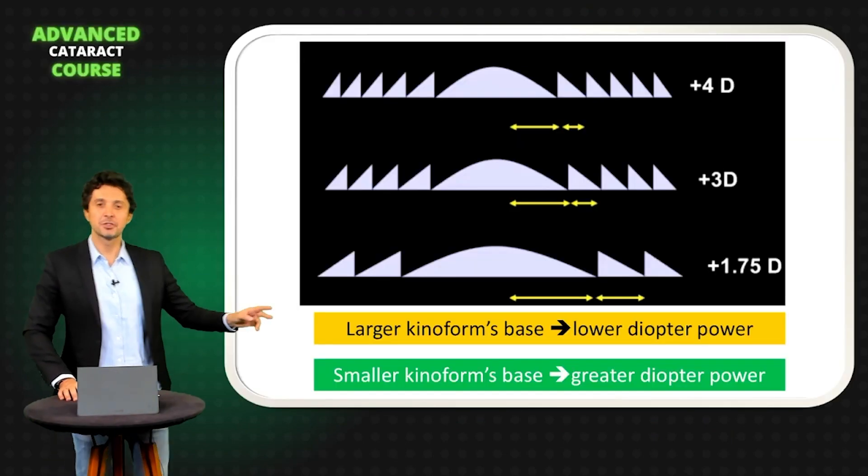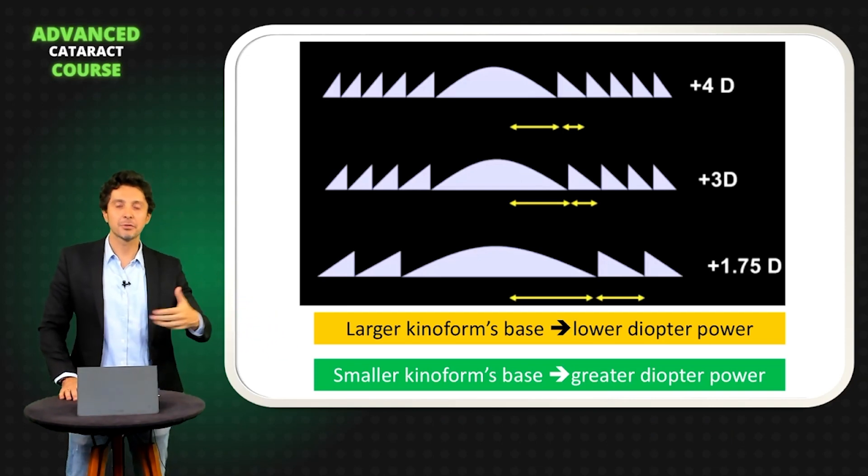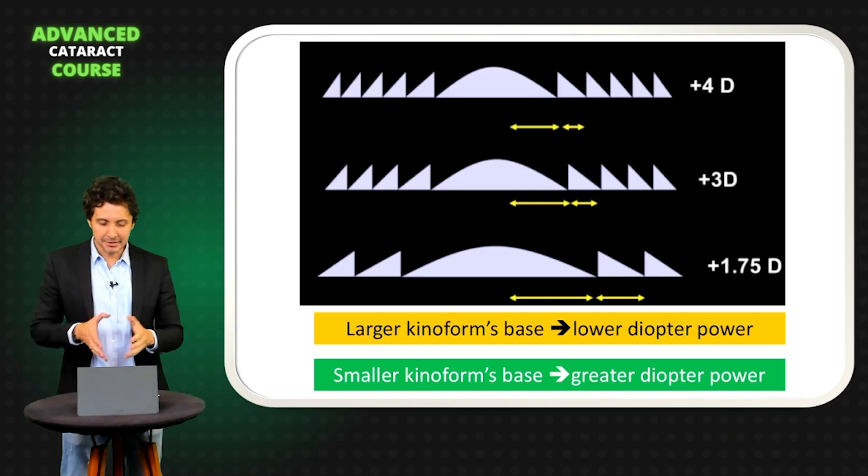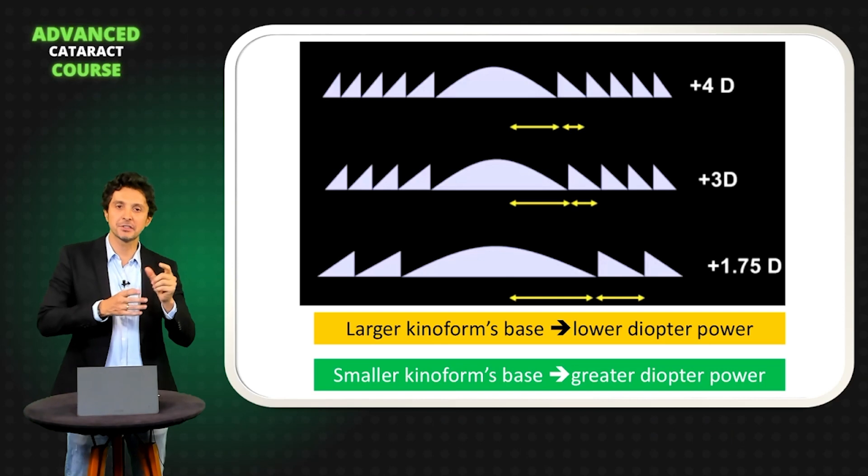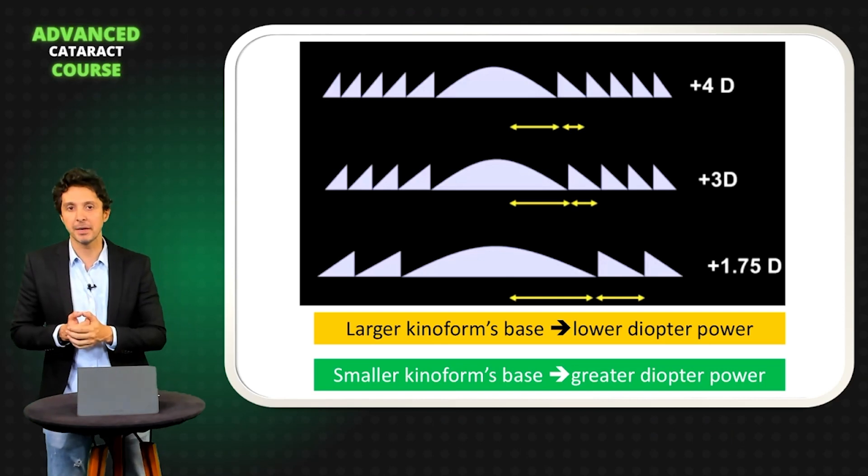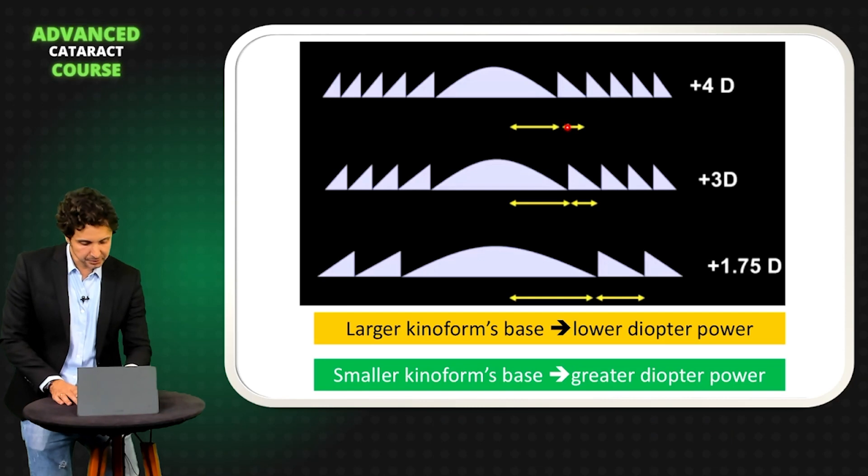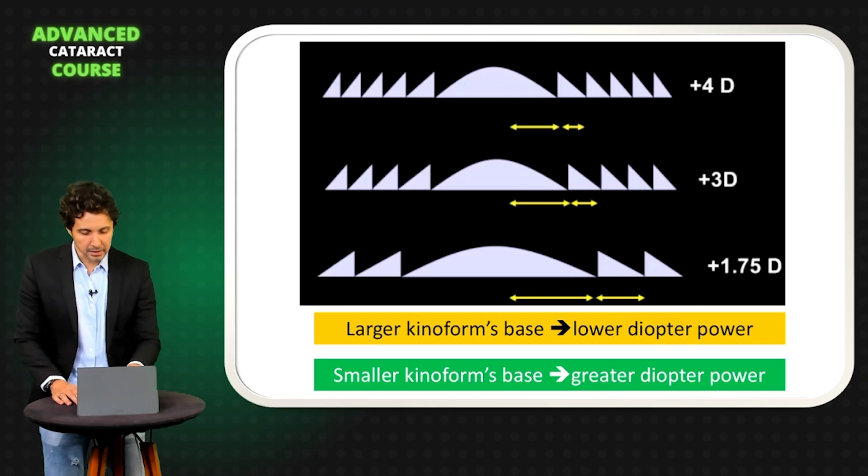Observe here. These two rules are important when you go to design a trifocal IOL. A larger kinoform base or larger diffractive ring base equals a lower diopter power. For example, this one. As you can observe here, this one is larger than these other two. So this one is 1.75 diopter.